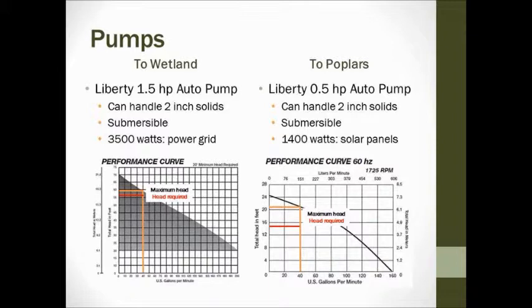These numbers were used to find the pumps we needed. We chose Liberty automatic pumps — automatic because the flow rate would be variable and we don't want to manually turn pumps on and off. We chose a 1.5 horsepower pump to the wetland and a 0.5 horsepower pump to the poplar plantation, based on the performance curves shown here. The orange line — the pump's maximum head — is above both the red lines representing our required head, which is good. These pumps can handle up to 2-inch solids, important since shower water will carry grit and dirt. Both are submersible, installed in the storage tank and collection pond. Power usage will be about 3,500 watts to the wetland and about 1,400 watts to the poplar plantation.